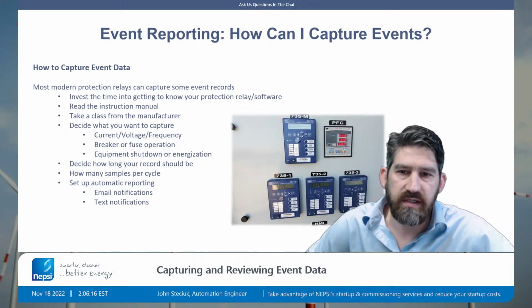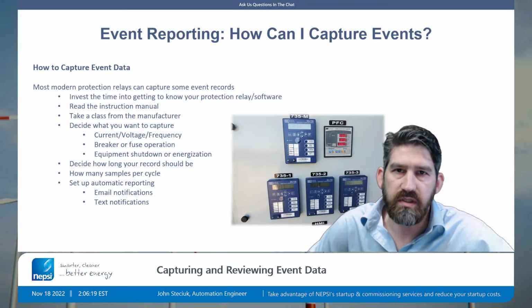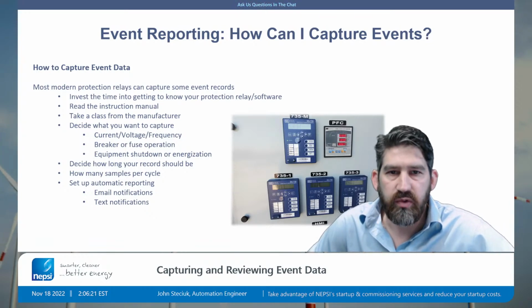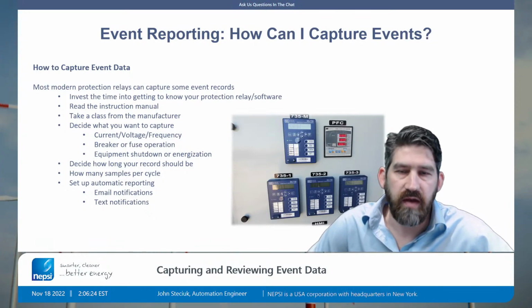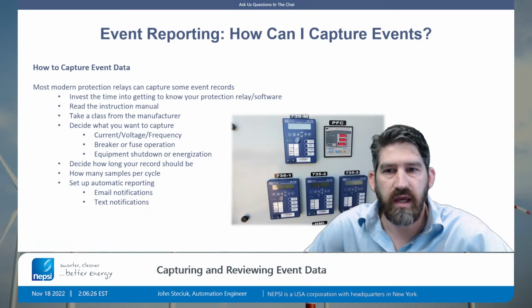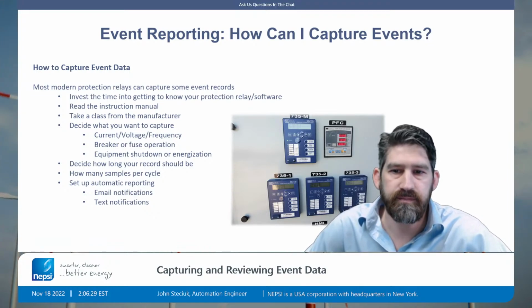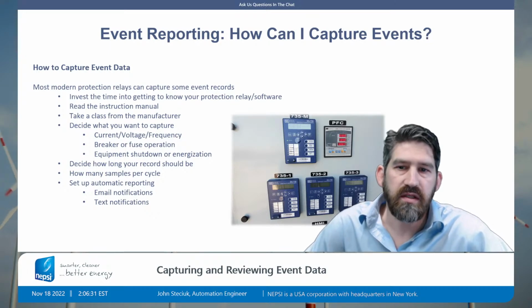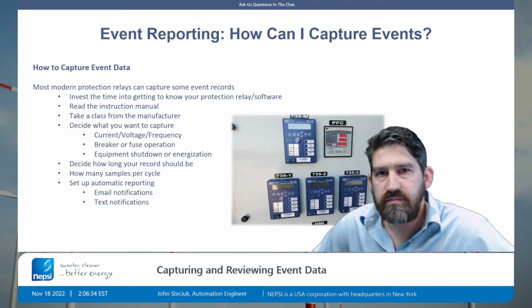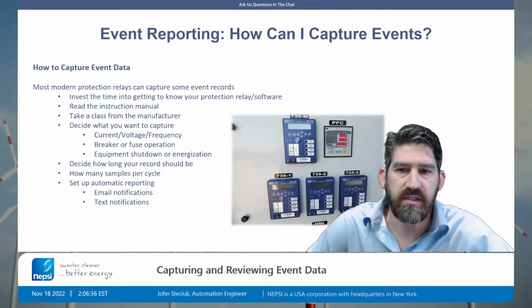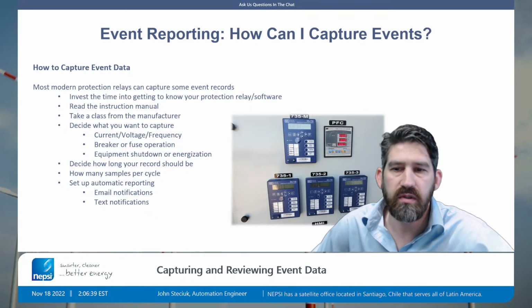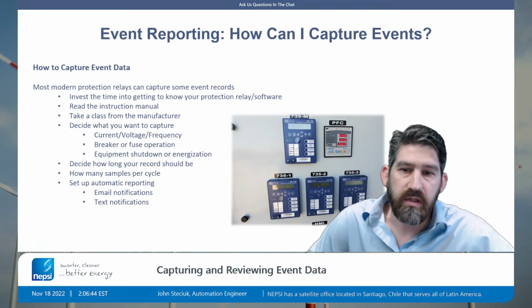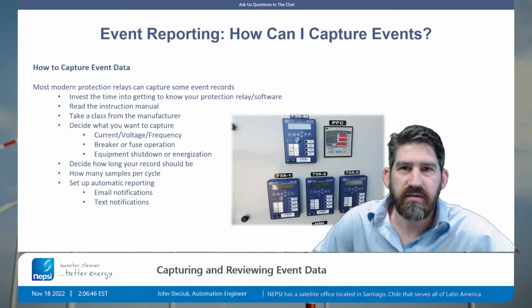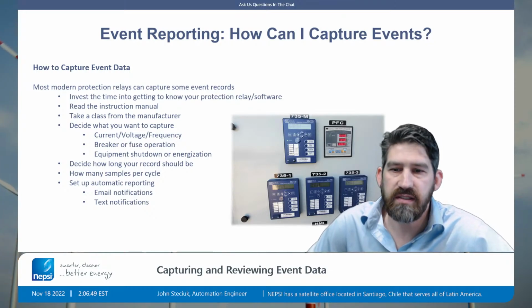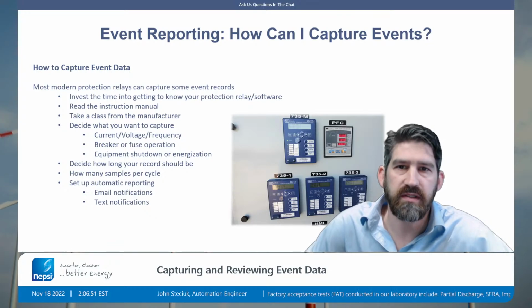Some other points, you need to decide how long your record's going to be. You can specify the pre-fault length and the after-fault length of the event capture, and some relays allow you to choose a resolution for the event, like how many samples per cycle are going to be recorded. Some don't have that feature. Another great one is setting up automatic reporting. It allows you to get an email or a text notification when there's been an event.